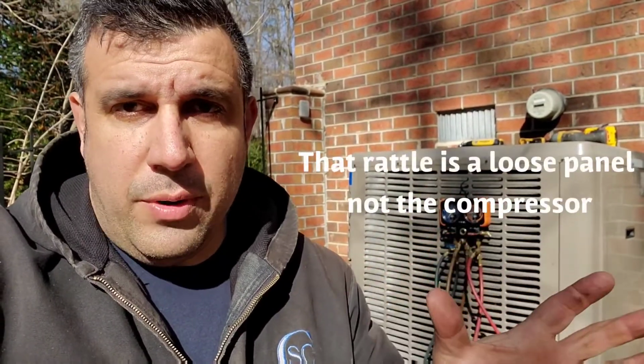Okay, so truth be told, I was actually the one that overcharged this unit, and it happened back in cooling mode. I made a repair, and I must have just put about a half a pound too much in there. MeasureQuick said it was okay, but it wasn't. And so I overcharged it slightly, and it didn't really affect it in cooling mode, but when I came back on a cold day to check it in heating mode, I saw it was not performing very well.